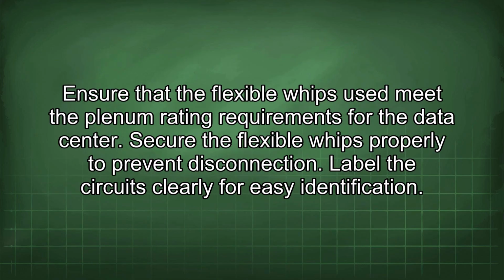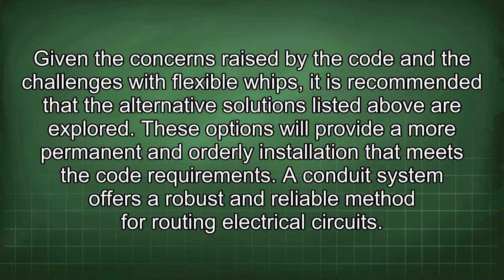Ensure that the flexible whips used meet the plenum rating requirements for the data center. Secure the flexible whips properly to prevent disconnection. Label the circuits clearly for easy identification. Given the concerns raised by the code and the challenges with flexible whips, it is recommended that the alternative solutions listed above are explored. These options will provide a more permanent and orderly installation that meets the code requirements.